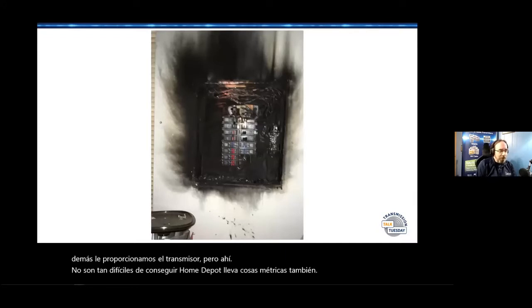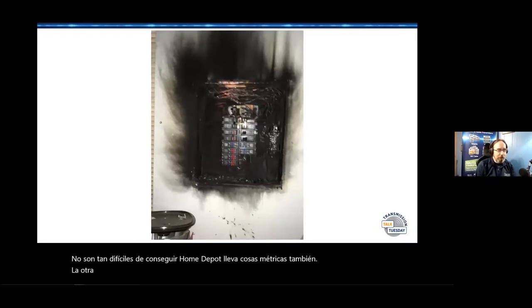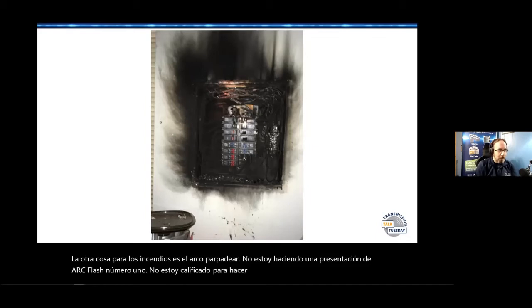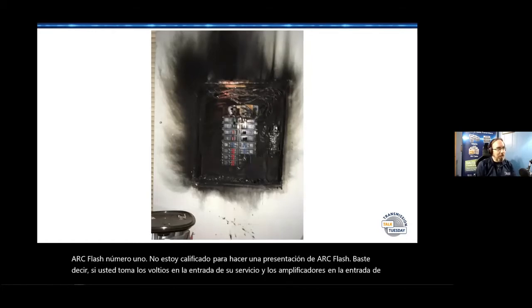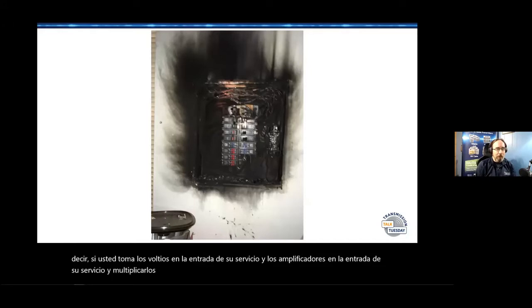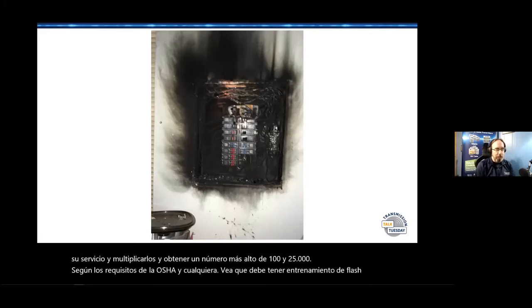The other thing for fires is arc flash. I am not doing an arc flash presentation, and I'm not qualified to do one. Suffice it to say, if you take the volts at your service entrance and the amps at your service entrance and multiply them, and get a number higher than 125,000, by OSHA requirements and NEC, you should have arc flash training and specific PPE on site.